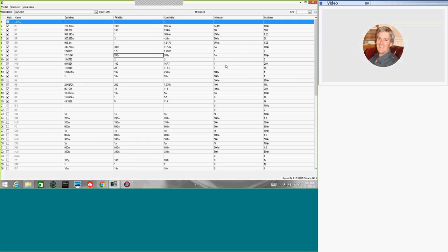it's the same. This guy plugs on, and these are C, and these are B. And for the back of the test fixture, remember how we put this on the probe station, we can use B and C because we have both triax and B and C feed through. But if I use a B and C to triax converter and plug that onto the back of that, will that work, or will that cause erroneous capacitance measurement?